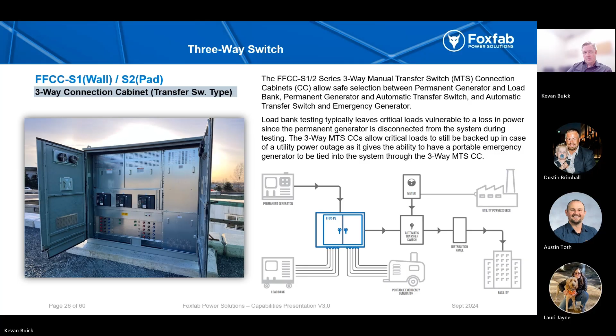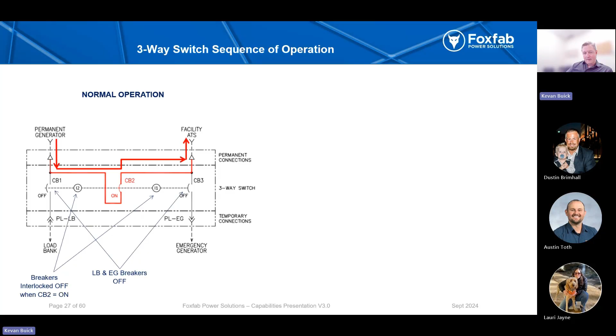So, and I'll just briefly pop into this. This is just the three-way switch sequence of operation. This is a product most are familiar with. It just gives you basically the isolation to have a load bank tied into your permanent generator and a temporary generator tied into your ATS, just as you'll see on the right-hand side there. So that's the bypass operation that most people seek when they buy this product, because it really does give you the best of both worlds. It gives you the ability to load bank, pulling that main generator offline while having a temp gen pulled in to make sure that there's no interruption in service.